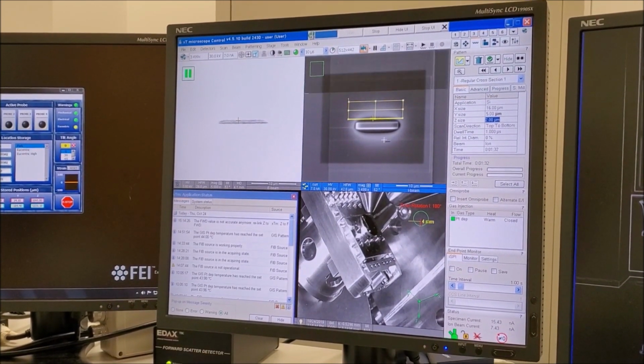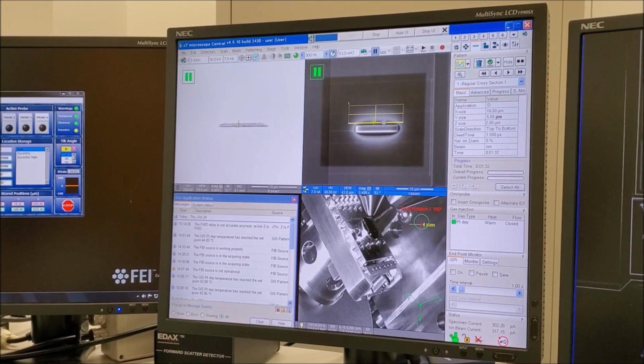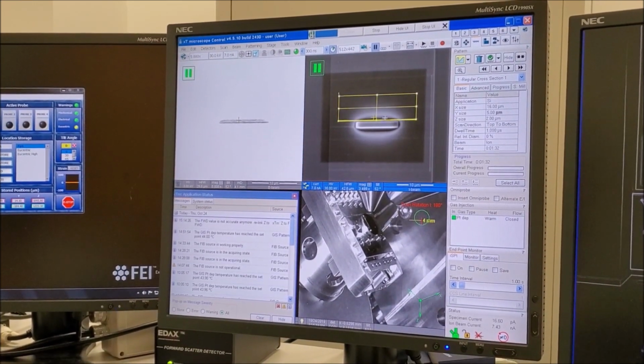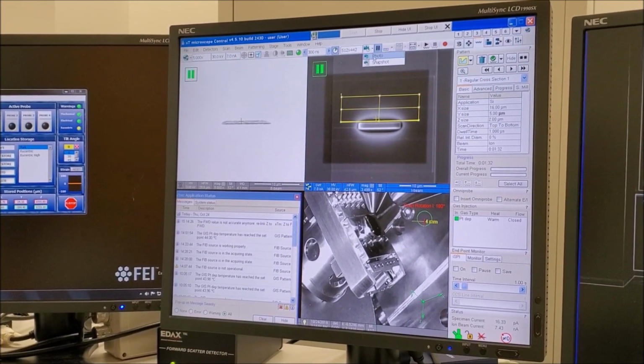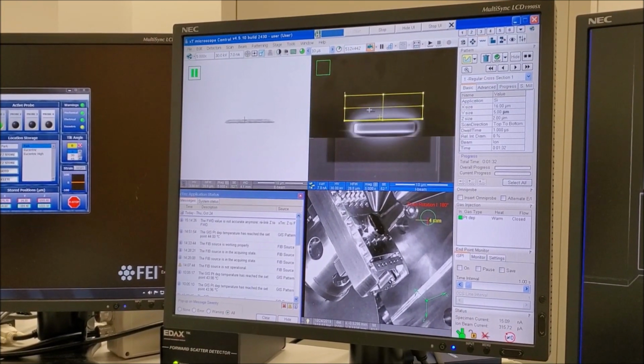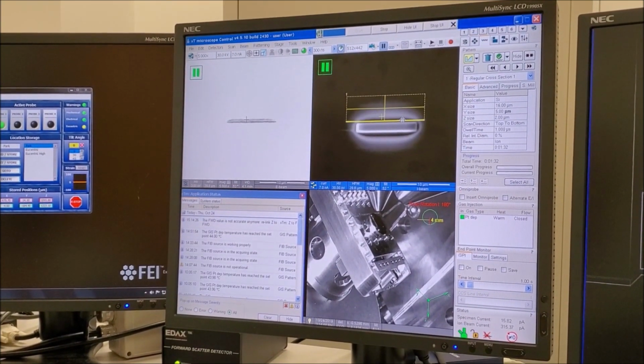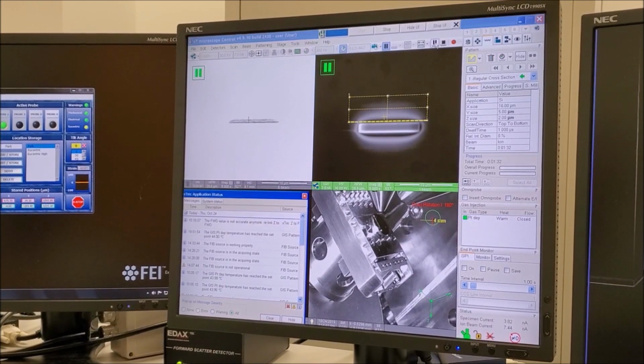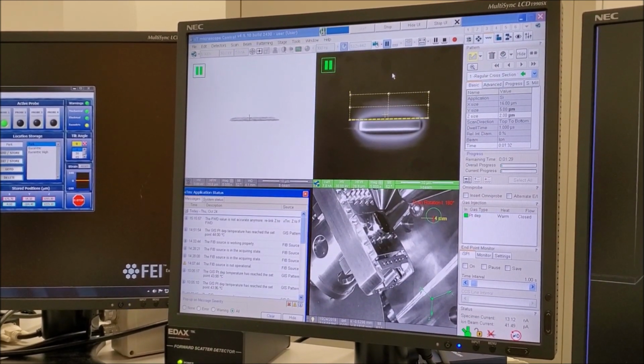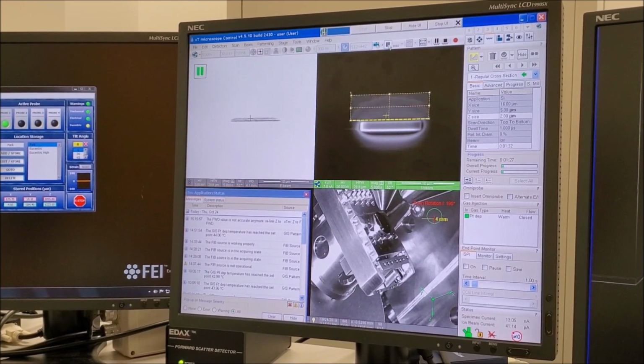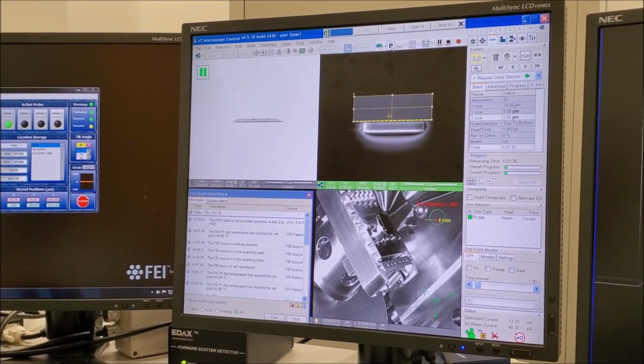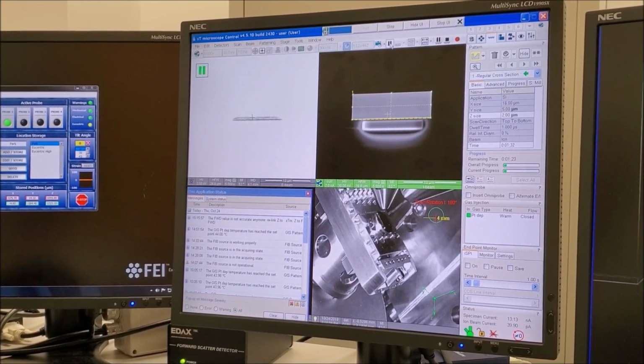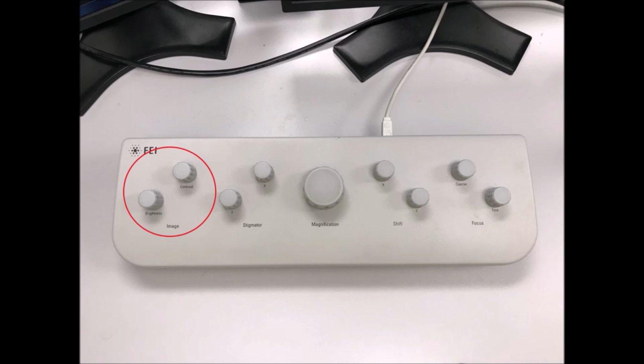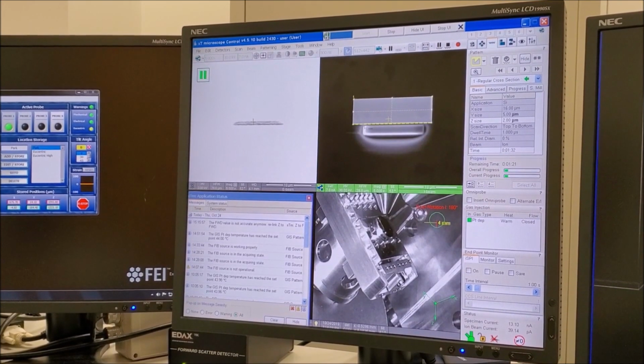Then take an additional ion beam snapshot and then click and drag on the pattern to position as needed. Adjust the magnification as needed, and again acquire another snapshot. Then select play to start the pattern. To view a live ion beam signal from the area that is being milled, activate the ion beam quad and then unpause. Then use the contrast and brightness knobs on the manual user interface to adjust so the signal is more visible.